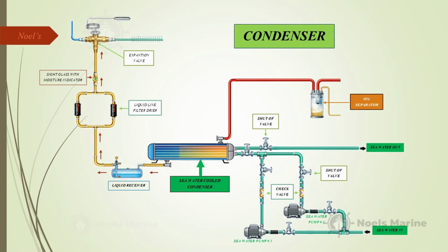And on a ship, we don't use giant fans like you would on a building. We use the ocean. Yes, the condenser is a heat exchanger cooled by seawater. Seawater flows through a series of tubes, and our hot refrigerant gas flows around them. And the heat just jumps ship, literally. It transfers from the hot gas into the colder seawater. Exactly. And as it loses that heat, it undergoes a phase change. It cools down and condenses back into a liquid. So it goes from a gas back to a liquid. Right. And the technical term for the output here is high-pressure subcooled liquid.